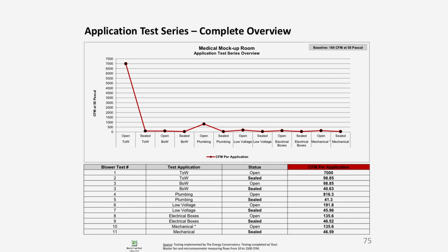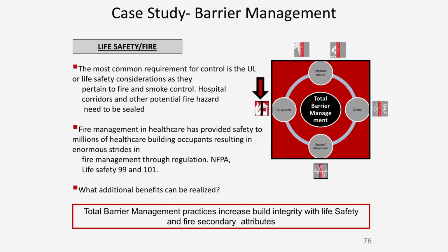What benefit do you get from that? You get better life safety. What does life safety mean? Fire management, smoke control. If our rooms are better sealed, we can get better safety measures for fighting fire, and you control the space and escape horizontally, but you combat the fire in place, because it's very difficult for us to evacuate a hospital, and we need to control that smoke, because fire doesn't kill, smoke kills. So we get one big benefit from a sealed building: better life safety.